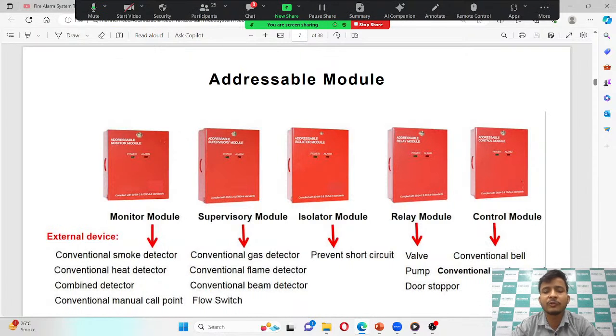Then we have the isolator module to prevent short circuits. If you are using detectors which don't have a built-in isolator, then these modules are required for protecting the devices from short circuits. After every 32 devices, an isolator module will be installed. Then we have the relay module for connecting a valve, pump, door stopper or PA system, as well as with the fire alarm system for giving an alarm in case of fire or emergency. It is basically used for hardware third party integration. Then we have the control module for adding a conventional bell and conventional sounder in the loop.